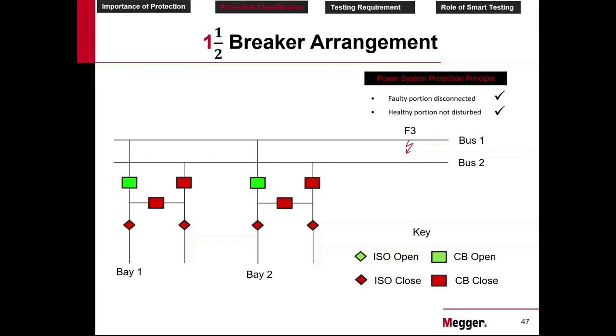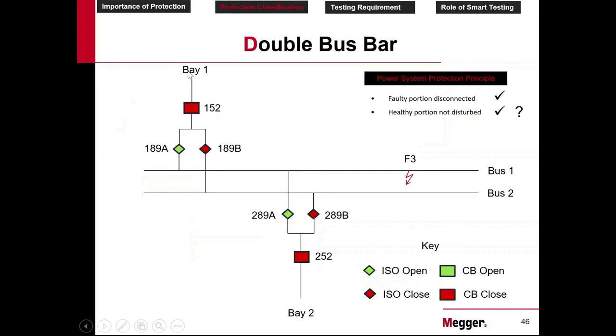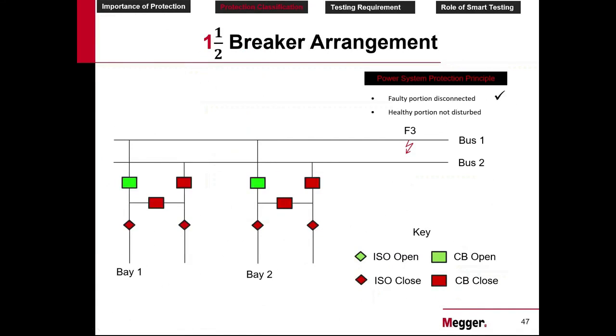However, we don't use it everywhere because you can see there are 3 breakers for 2 lines, whereas in the earlier example, we had only 2 breakers for 2 lines. Just see this example. For 2 lines, bay 1 and bay 2, this bay is also called a line. So for 2 bays, you have only 2 breakers. Whereas here, we have shown 2 bays. Bay 1, bay 2, maybe bay 3 or bay 4. You can use a different name. So you need 3 breakers for 2 bays. So 3 divided by 2, it's 1.5. That's why it is called the 1.5 breaker arrangement.